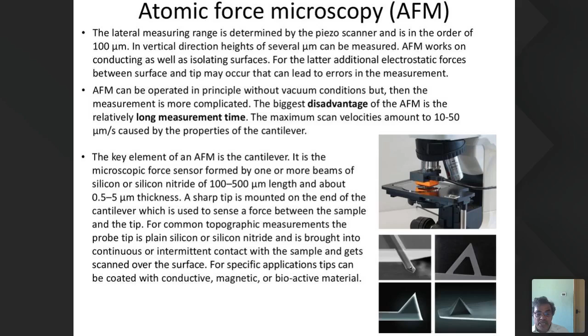Okay. The key element here is the cantilever. It is a microscopic force sensor formed by one or more beams of silicon or silicon nitride of 100 to 500 micron length and about 0.5 to 5 micron thickness. A sharp tip is mounted on the end of the cantilever, which is used to sense the force between the sample and the tip. For common topographic measurement, the probe tip is plain silicon or silicon nitride. For specific applications, tips can be coated with a conductive, magnetic, or bioactive material.